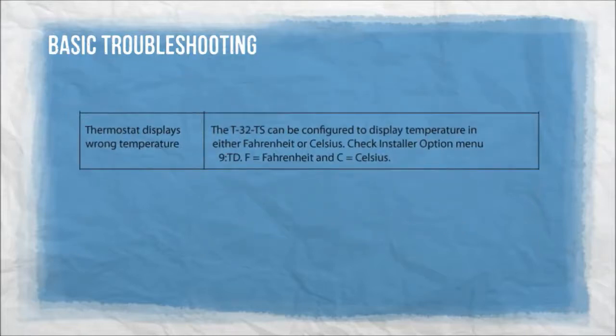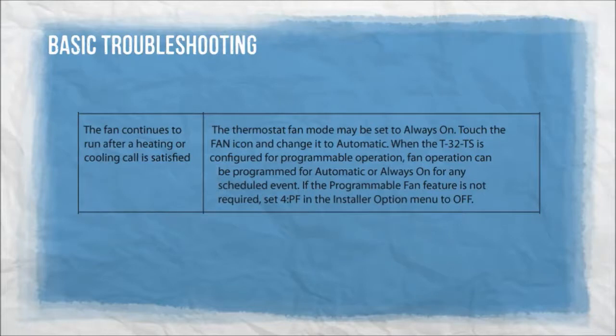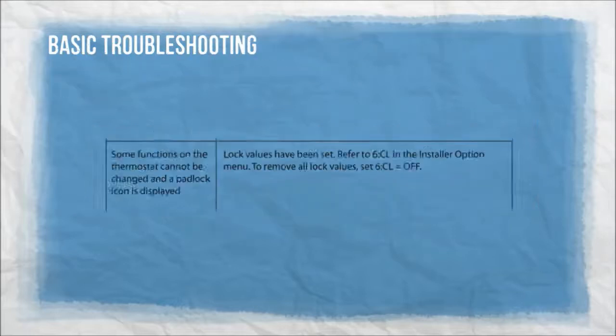Thermostat displays wrong temperature. The T32TS can be configured to display temperature in either Fahrenheit or Celsius — check installer option menu 9TD: F equals Fahrenheit, C equals Celsius. The fan continues to run after a heating or cooling call is satisfied. The thermostat fan mode may be set to always on — touch the fan icon and change it to automatic. When configured for programmable operation, fan operation can be programmed for automatic or always on for any scheduled event. If the programmable fan feature is not required, set 4PF in the installer option menu to off.